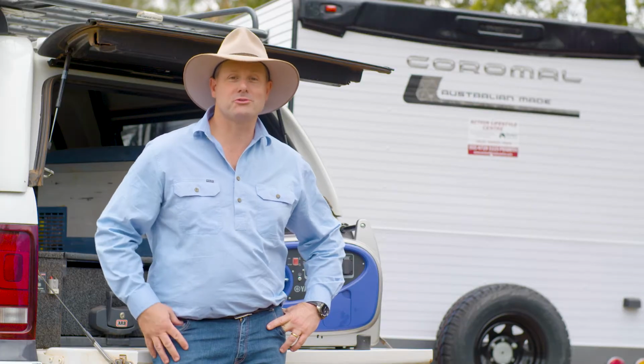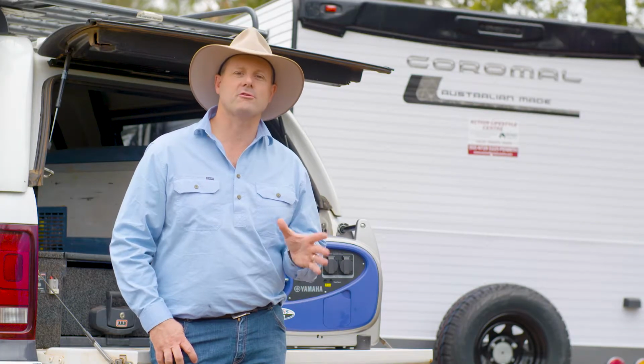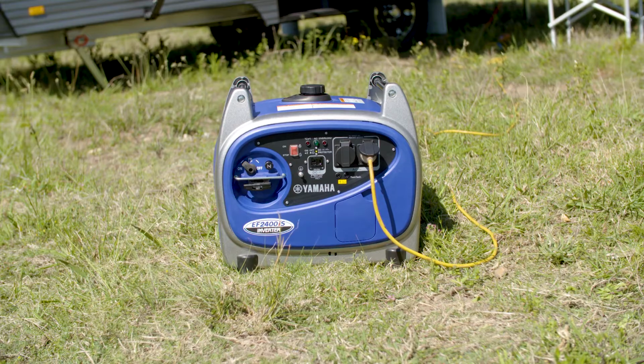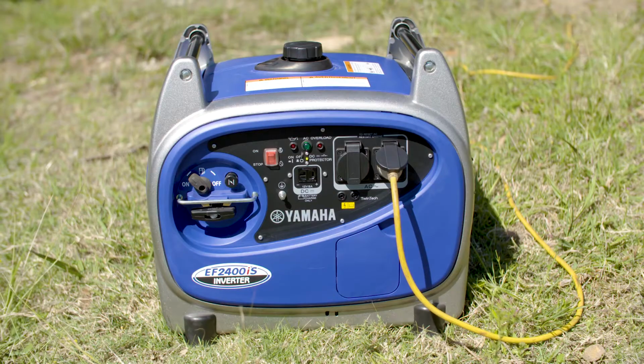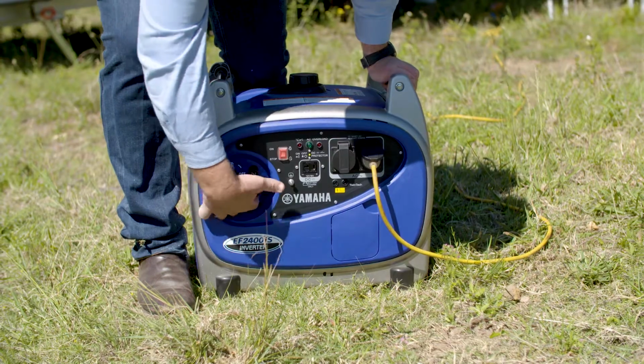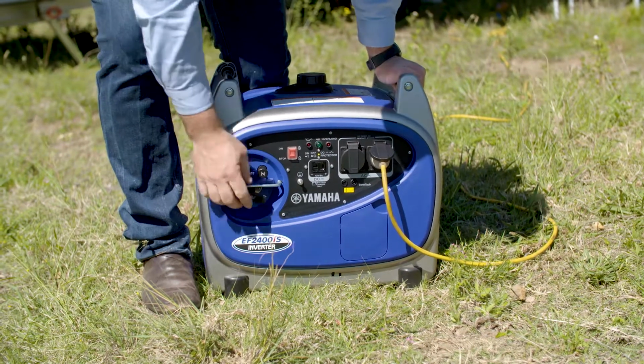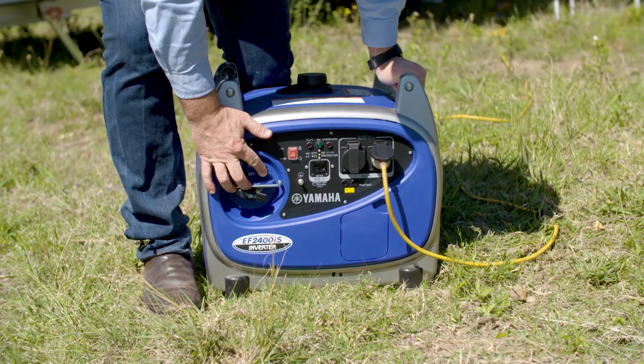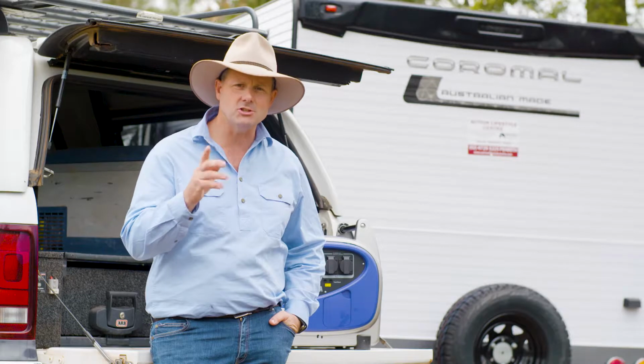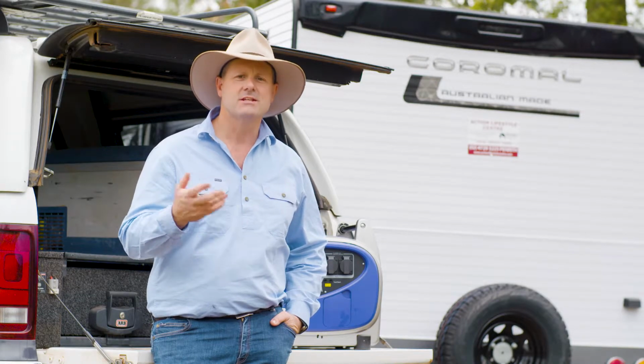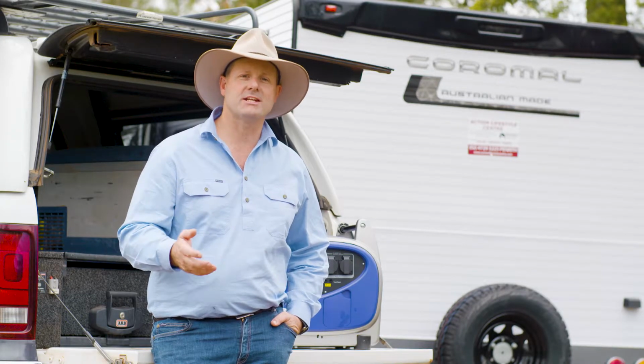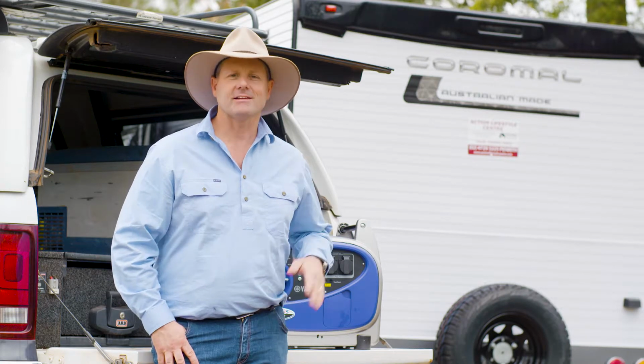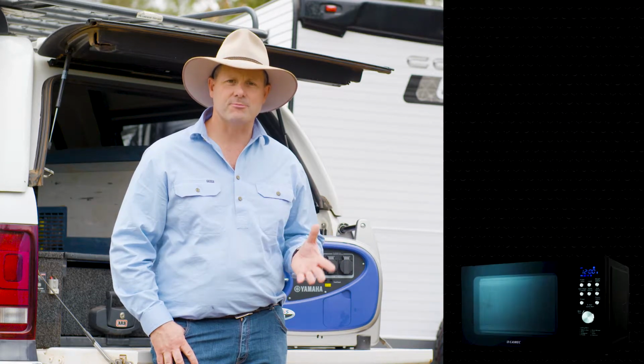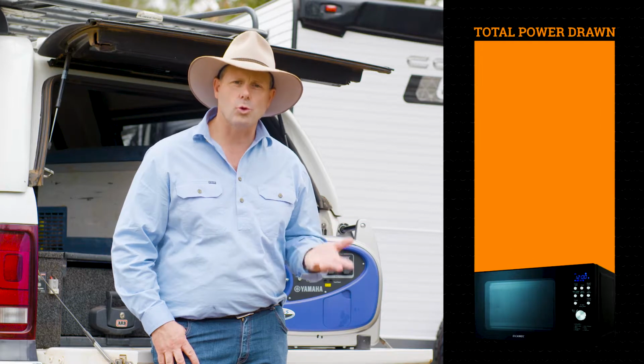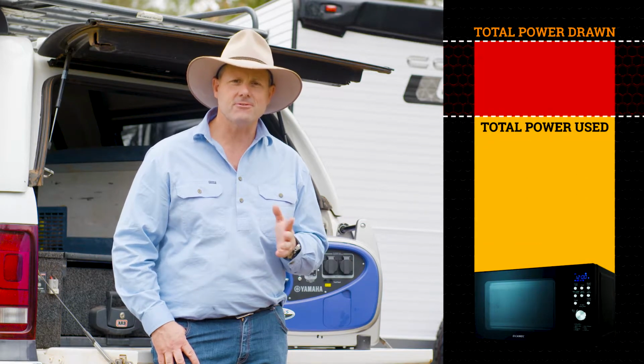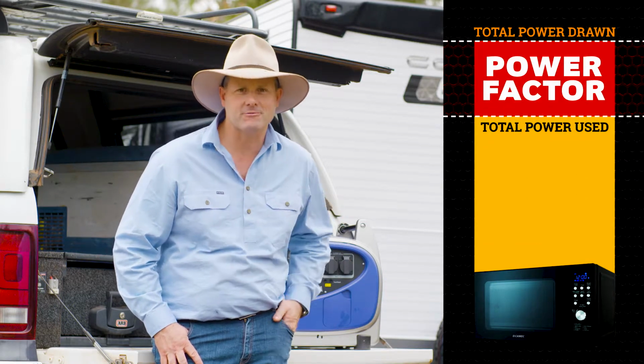For years, a portable generator has been the go-to 240 volt power source when it comes to bush camping. Generators come with different output ratings, so choosing the one you need depends on how you use it. Jennies are rated in kilovolt amps, but you want to convert that into watts to figure out what equipment the jenny will comfortably power. Electrical gear draws a certain amount of power, but rarely consumes all the power they draw. The difference is known as the power factor.